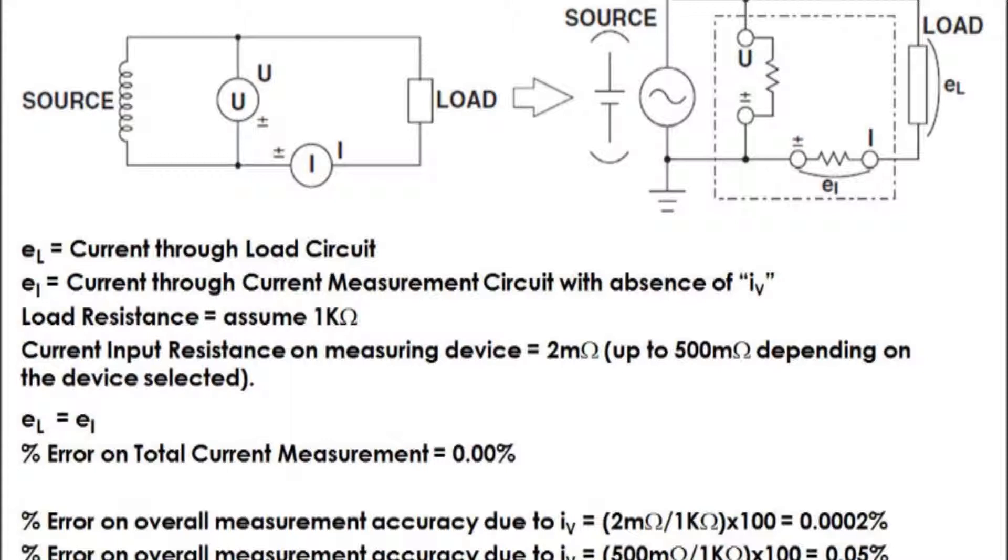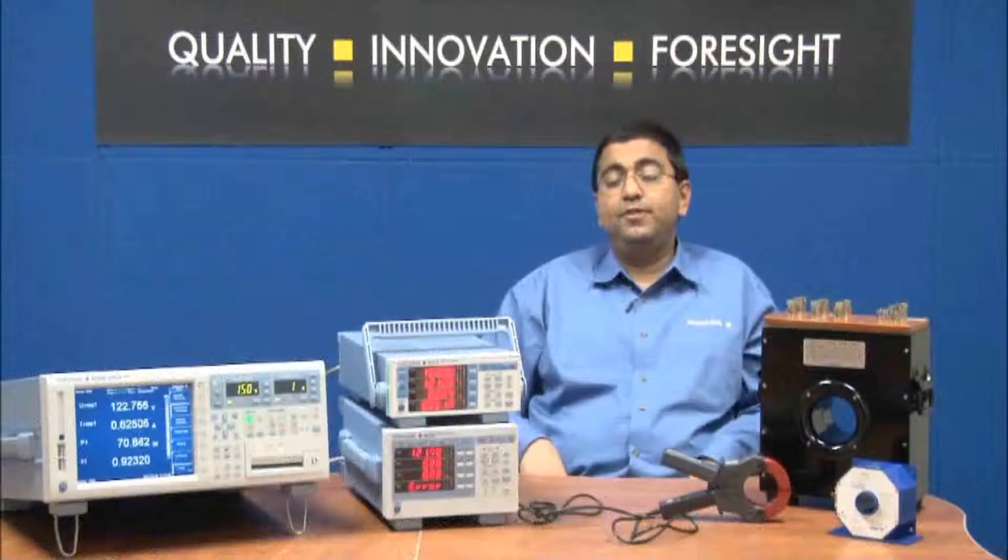You may argue that this arrangement could affect the voltage measurement and in turn could also affect the overall accuracy. Well, not much. On Yokogawa power analyzers, the input resistance of the current measuring device is very low. The input resistances range from 2 milliohms to 500 milliohms depending on the device selected. So the voltage drop across this resistor would be very small and the effect on the overall accuracy would be minimal.